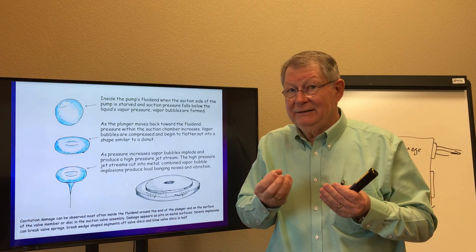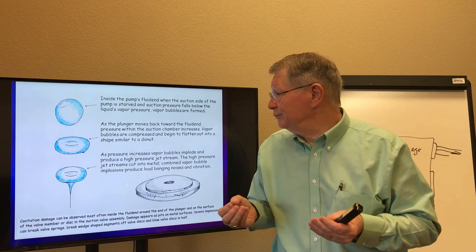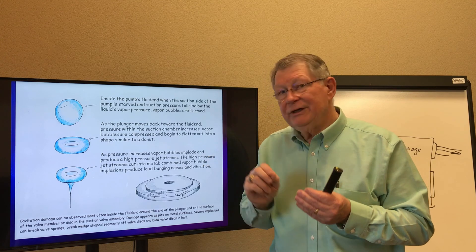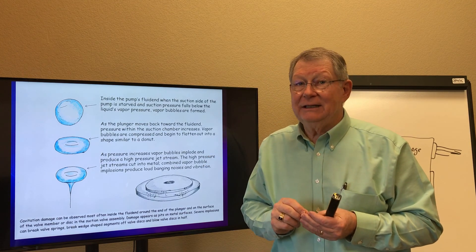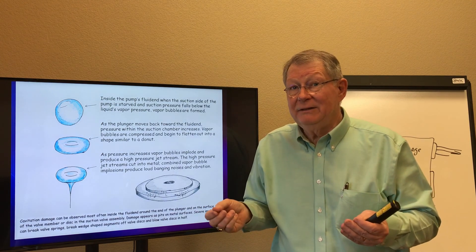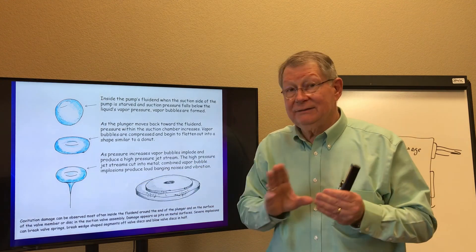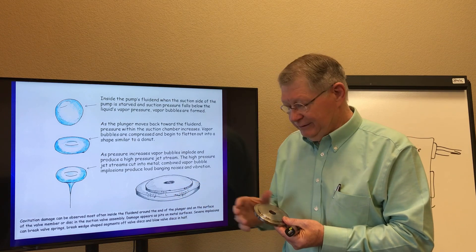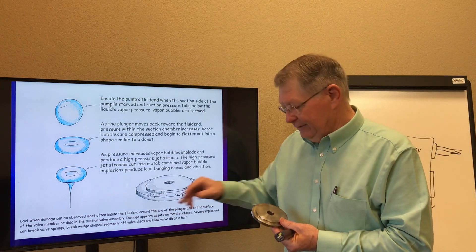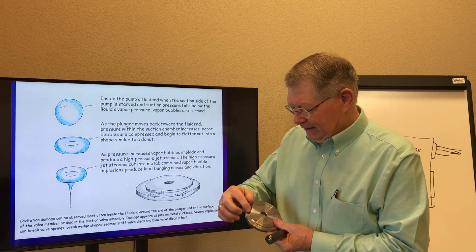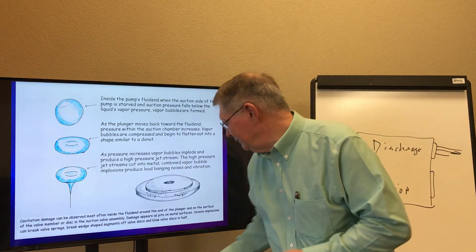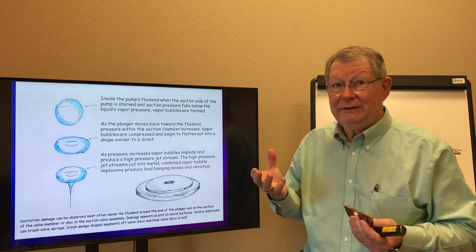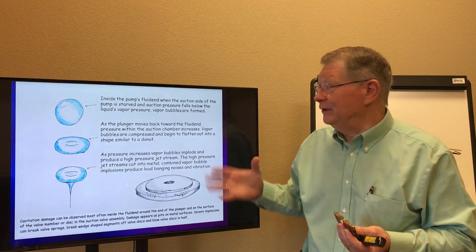Think about this — we're talking about many thousands of vapor bubbles forming during this process. As they implode, they create a high-pressure stream of water. This water is at very high pressure and it cuts metal — like a CNC water jet that can cut through three, four, five, or six inches of metal very easily. Cavitation does the same thing and is terribly destructive. You get the noise — the bing, pop, bang — and the vibration from these implosions inside the pump.